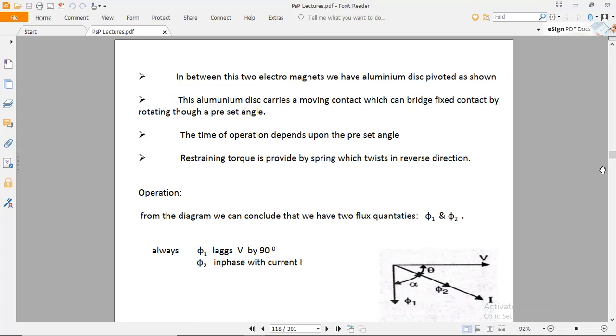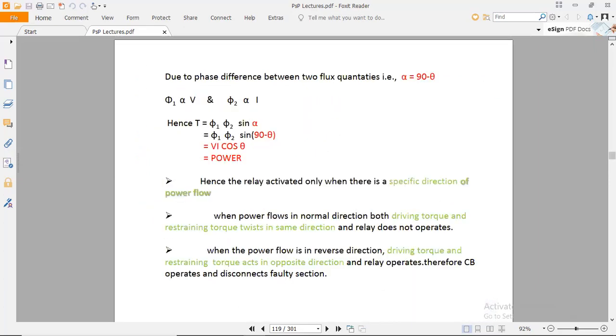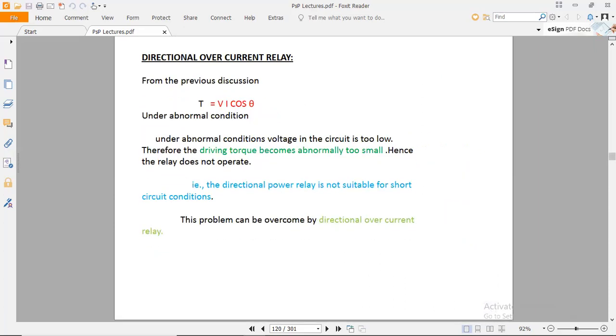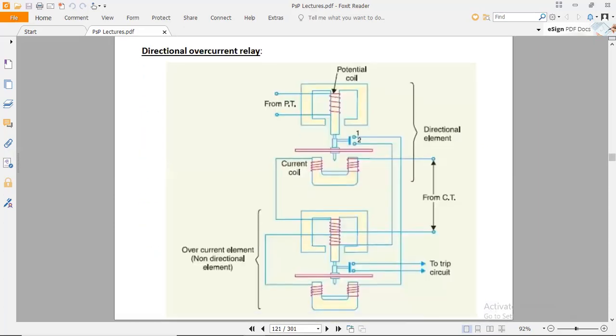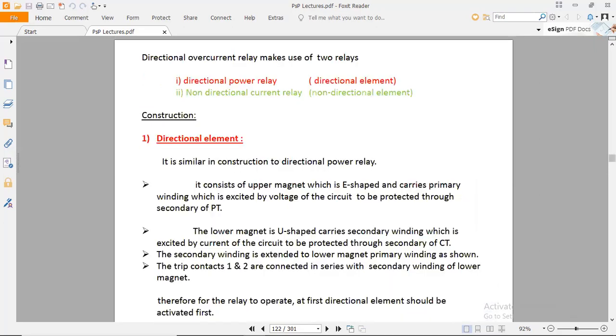So the spring can restore its force, and in the opposite direction the disc would again reach its original position by the restoring force performed by the spring mechanism. So this is the theoretical concept, which is also explained here. The directional overcurrent relay can also be set with this coil. So we already discussed a simple scenario.